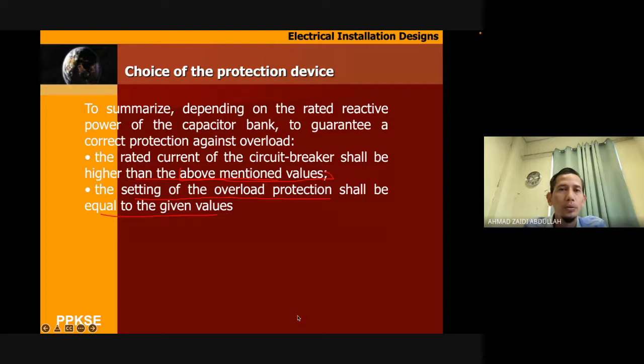Alright, to summarize, depending on the rated reactive power of the capacitor bank, to guarantee protection against overload, the rated current of the circuit breaker shall be higher than the above-mentioned value. So the value of the capacitor and the circuit breaker, as normal, IN must be higher than IB. And then the setting of the overload protection should be equal to the given value. So the setting under the PFR, and also the breaker. If you have a setting, you must set it equal to the given value.